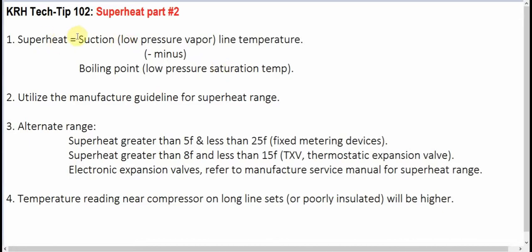So superheat is the suction line temperature as measured with a thermal clamp on the suction pipe minus the boiling point or low pressure saturation temperature, which is the temperature the refrigerant's boiling at in the evaporator, which will be indicated on your low pressure gauge. Regarding superheat, we would prefer to utilize the manufacturer guideline for the superheat range for that system.